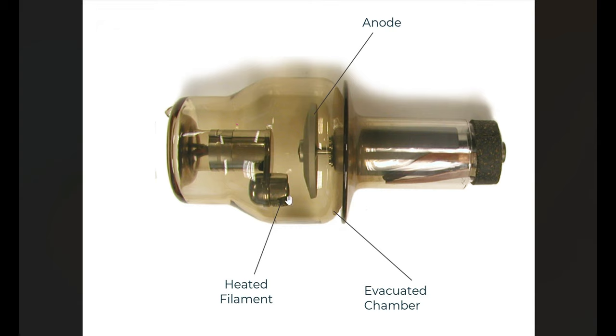Coming back to our x-ray tube, we have our heated filament where the electrons come off and are accelerated towards the anode across this gap. That anode is held at a positive charge, and the voltage difference between the negative cathode and the positively charged anode — the higher that voltage difference, the faster the electrons move and the higher energy the x-rays we produce will be. If we increase the mAs, we increase the number of electrons accelerated towards the anode, increasing the number of x-rays generated. So that's KV and that's mAs.